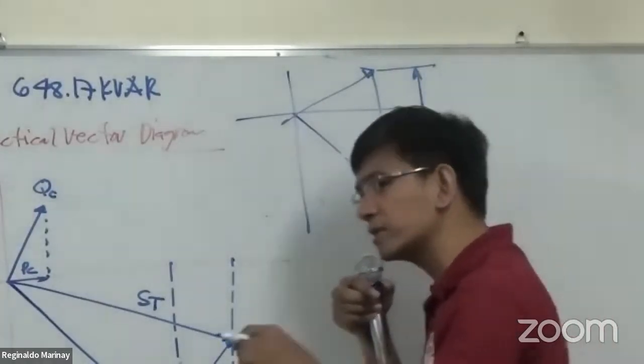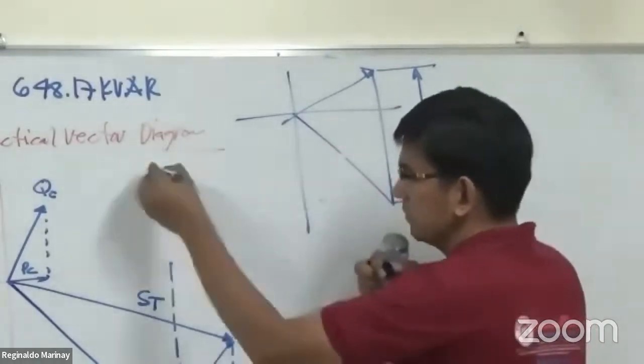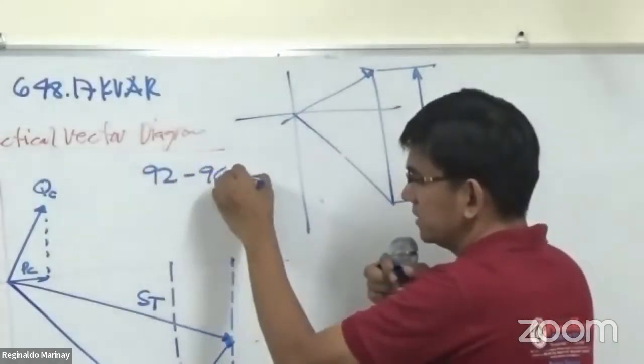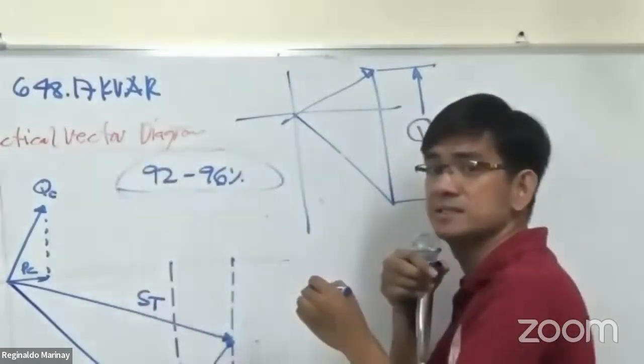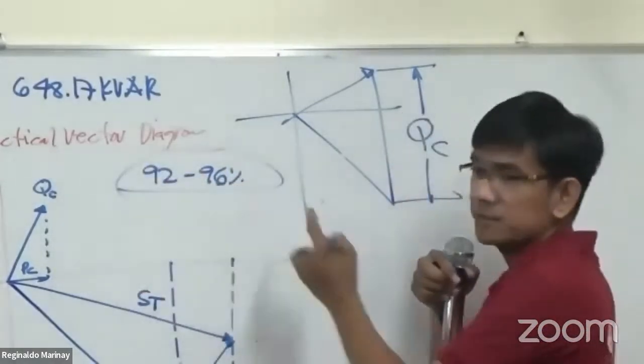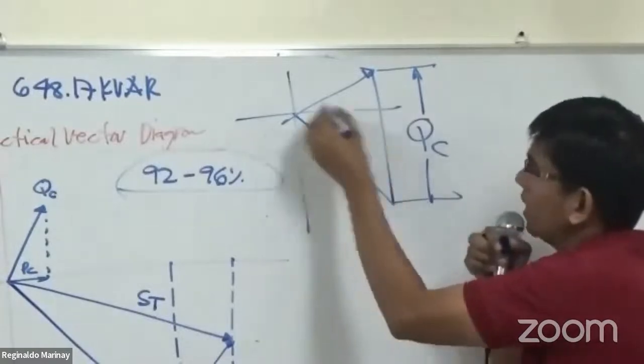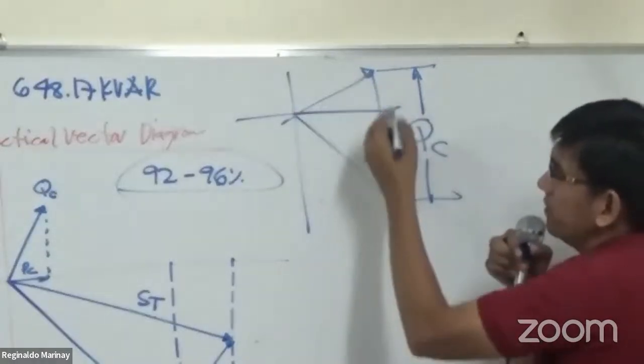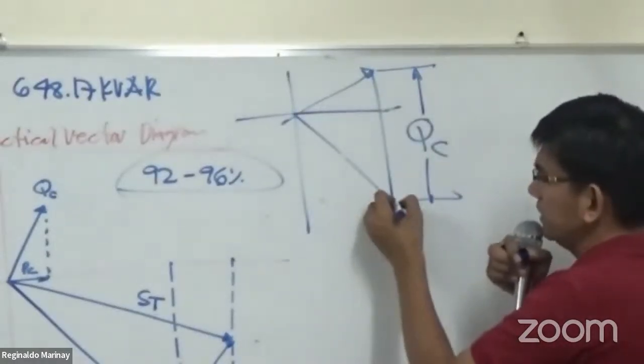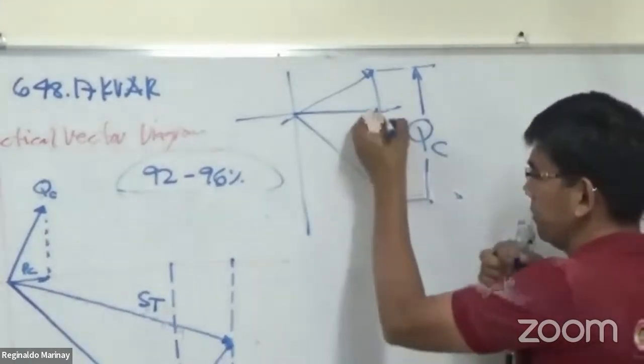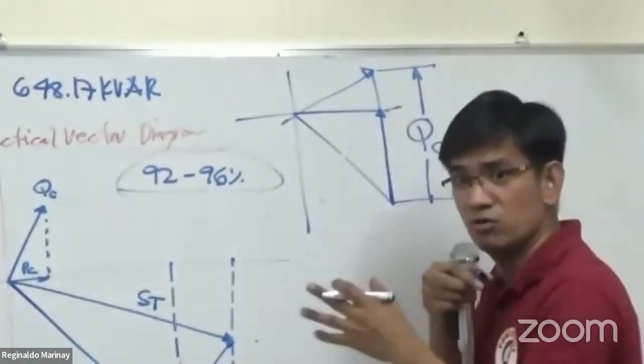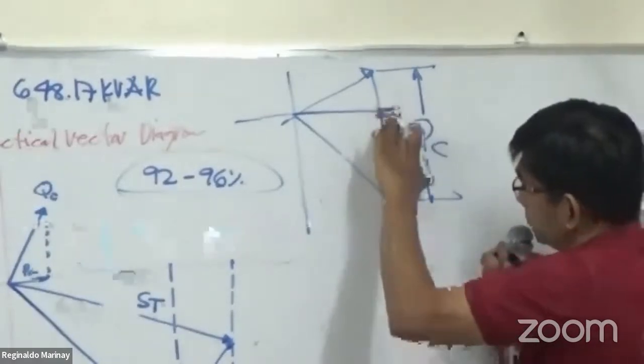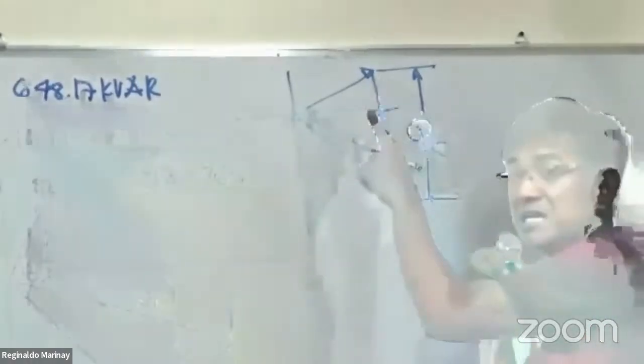Okay, so you have to be careful. If you are going to correct the power factor, advisable 92 to 96%, based on our experience, that's a good power factor. At unity, if it's already at 1, you're already beyond it. When we say unity power factor, up to this point, meaning the angle is 0. But if you go beyond this point, that is already a leading power factor, and that is not good.